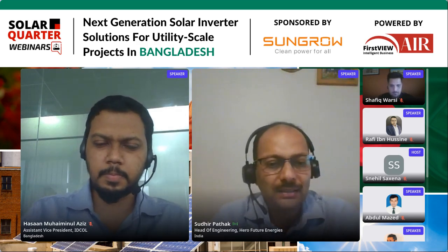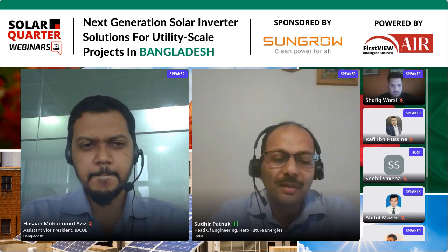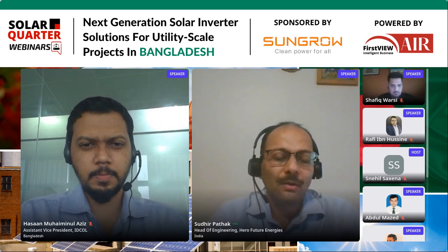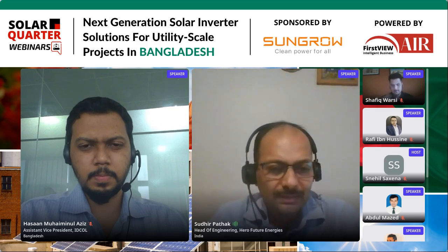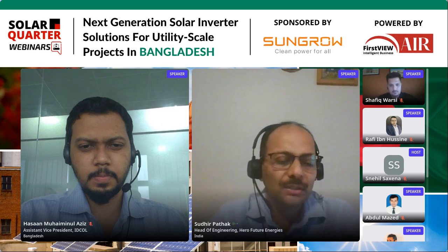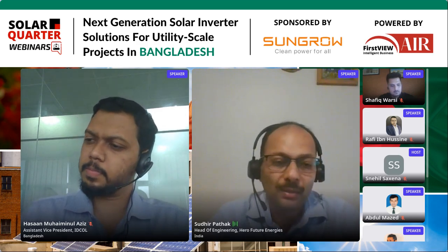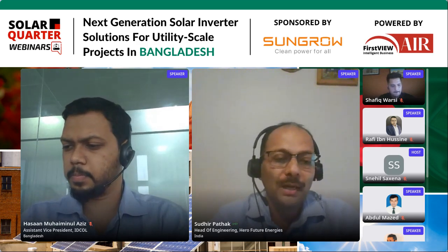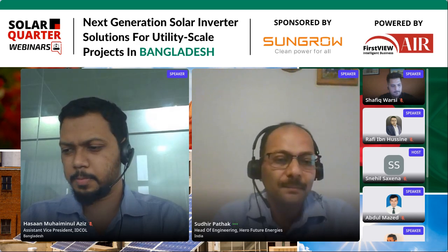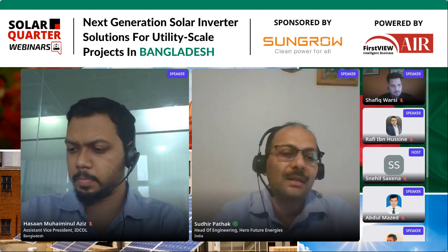However, we have seen at several locations in Bangladesh some hilly regions. So from that perspective, one has to be very, very selective. In case you are going on land which is quite monolithic, quite flat, then you should go for a bigger size. And as far as efficiency is concerned, the technology has now got so matured. Initially it came with a two-level topology, then three-level, now it is quite common. Now even people are talking about five-level also, right? Four and five-level topology, and even silicon carbide, SiC-based inverters, which are much more efficient.